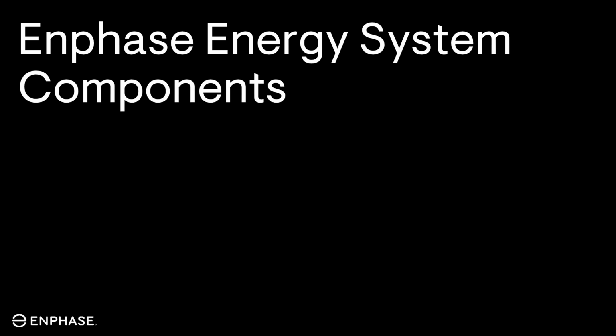I wonder if they're talking about rapid shutdown. So with the IQ8 and any kind of backup power configuration, you have to use the IQ System Controller 2 and also install a rapid shutdown switch that Enphase provides. And when that rapid shutdown switch is activated, it opens the relay for the PV and disconnects the PV, which has been approved as a rapid shutdown. I mean, it's an approved rapid shutdown method for our system. So I do have some content specifically about rapid shutdown, and hopefully once we get to that, it'll help clarify a couple of things.